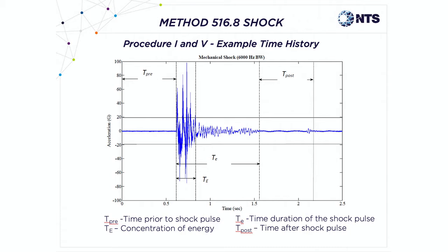Then we can hold TE pretty well. But if no research is being done, you need to hit the curve across the whole frequency range. We will exceed TE, most labs will, but there is some mathematics in there to calculate so you don't exceed the TE by too much. So we do prefer the SRS method over the sawtooth method, but if you still prefer to do the 20G sawtooth or the 40G sawtooth, depending on the vehicle, that's fine as well. So that's P1 and P5 sort of combined together.